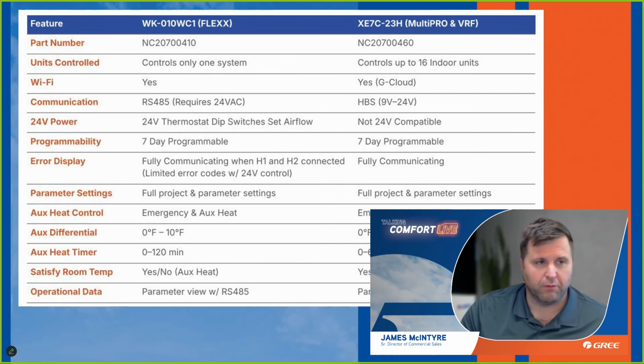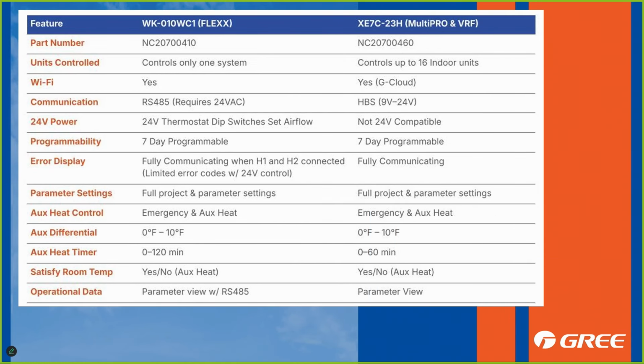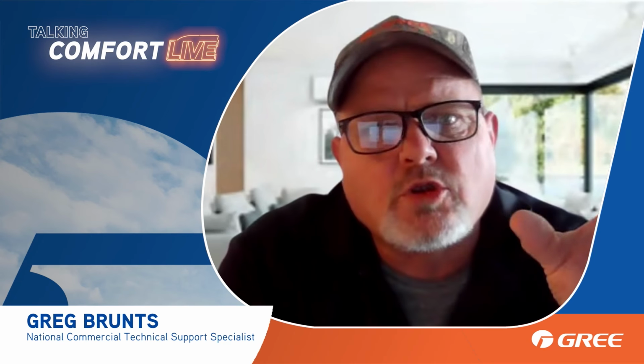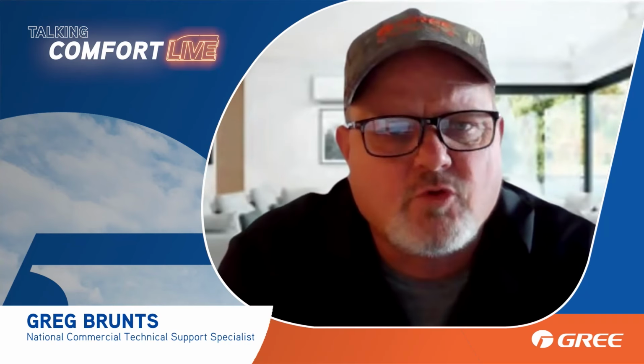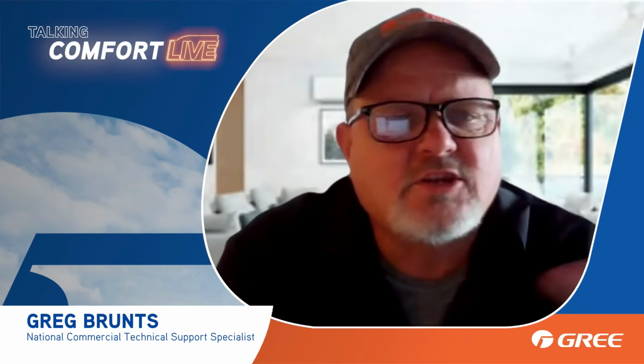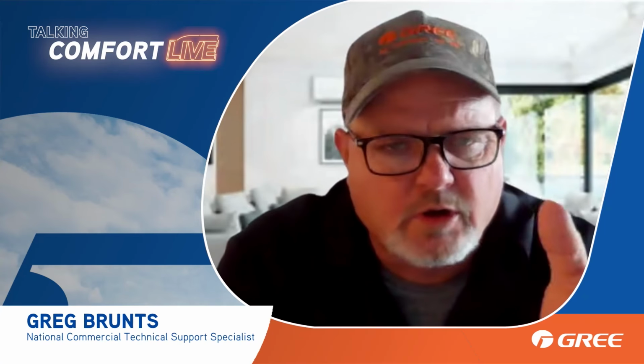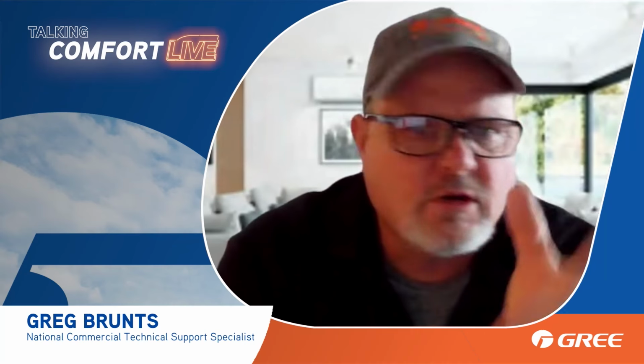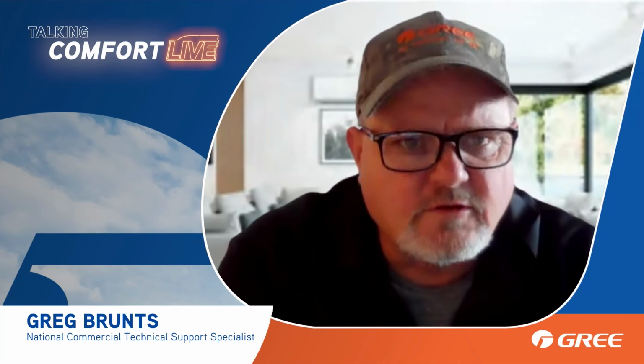So we've got one inexpensive solution for that, which is a G Cloud, which can also control up to 16 units. With a MultiPRO system, the maximum amount of indoor units you can connect to is 10. But you'll be able to add all 10 units at once pretty quickly through the G Cloud app. Let's be a little more clear with that. When you've got more than one indoor unit, it's a system, and you want system control of all the indoor units. You can't do that just off of one wired controller, because if one wired controller is hooked up and only controlling one head, you're not controlling the system. That's why you need the G Cloud.